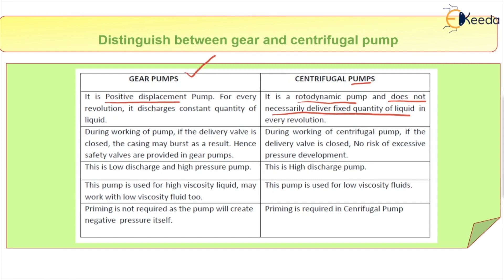Regarding safety: during working of the gear pump, if the delivery valve is closed, the casing may burst as a result. Hence, safety valves are provided in the gear pump. Because it always delivers a fixed quantity, a blockage can cause excessive pressure and the casing may burst. That is why a safety valve is essential.